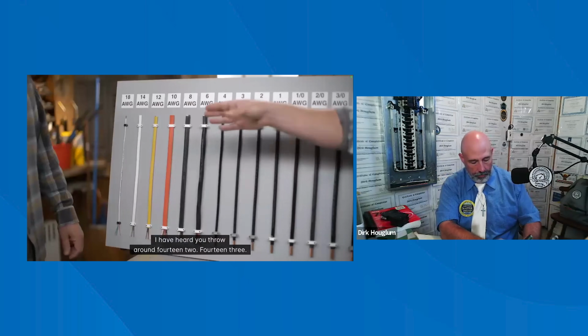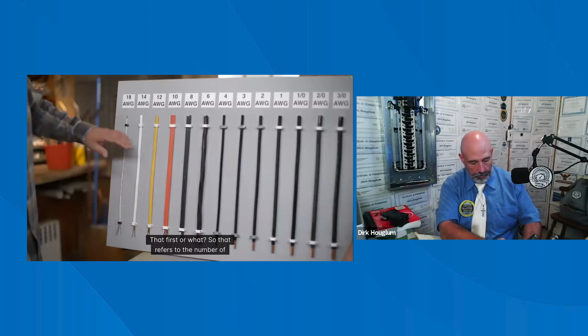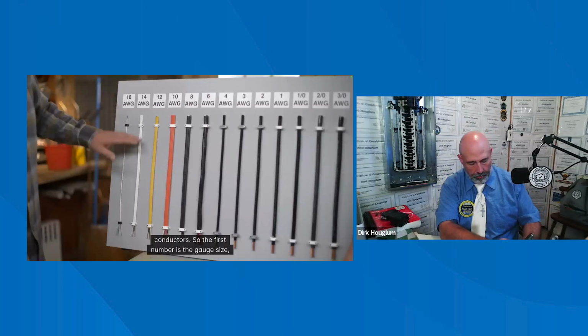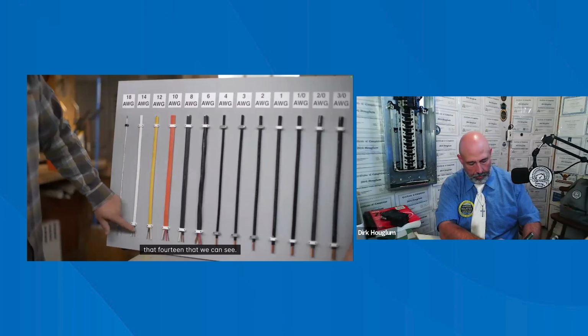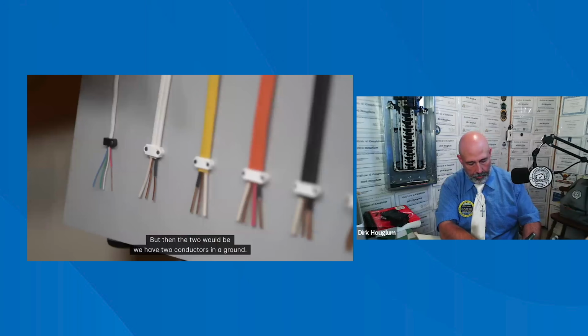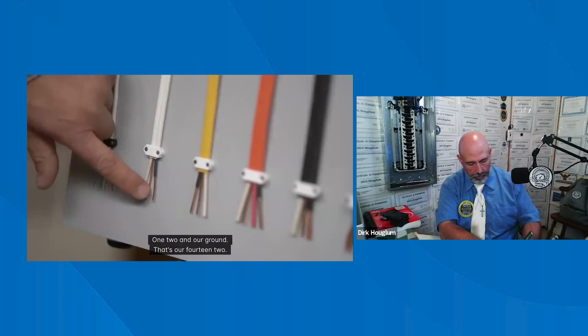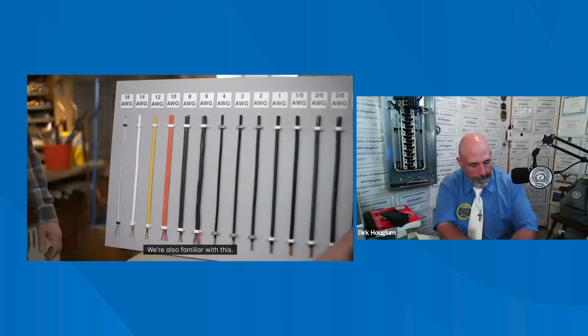I have heard you throw around 14-2, 14-3. That refers to what? So that refers to the number of conductors. So the first number is the gauge size, that 14 that we can see. But then the 2 would be we have 2 conductors and a ground. So 1, 2, and our ground. That's our 14-2. And so there might be a third conductor if you have that three-way switch or something like that. Exactly. But it's still the same size. Same size, just more conductors in the jacket. Okay.